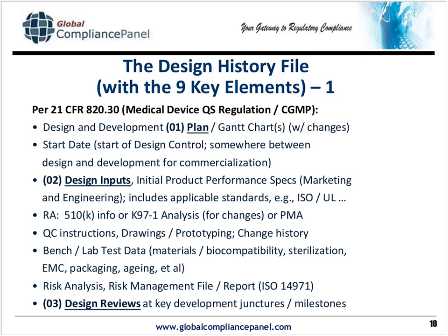Design inputs. Those of you that have been audited by the FDA know that whenever they look at any kind of validation documentation, they want to see what the requirements were, and then they want to see that your testing, your verification steps met or addressed every one of those requirements. So when you're talking about design control, you're talking about what are the design inputs, what are the issues you are trying to address in developing this new product or this major line extension of an existing product.